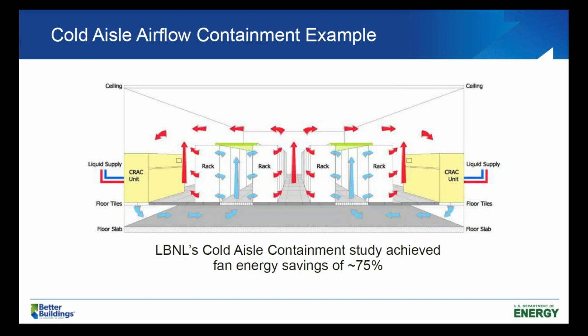Okay, so here's a cold aisle containment example where you put basically a lid on top of the racks in the cold aisle, and then also doors at the ends, and that keeps that air from becoming bypass air. We did a containment study and showed that we could get fan energy savings on the order of 75%. Next slide.